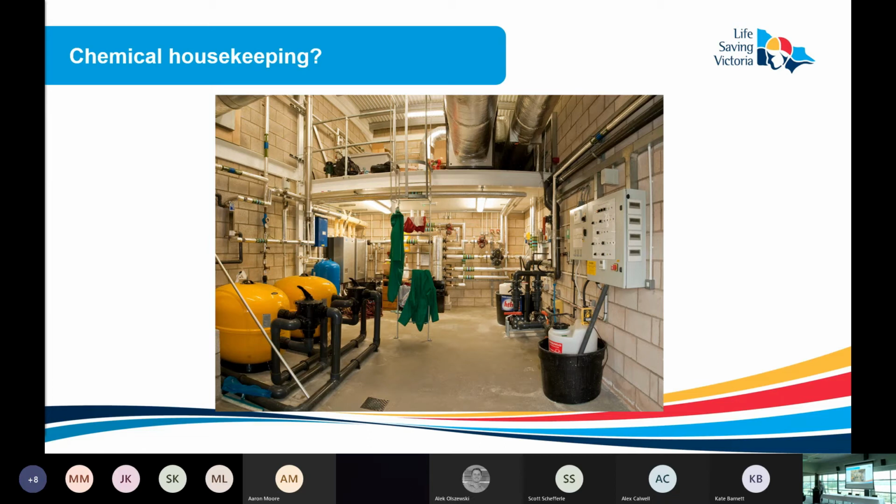You've got regular chemical bunds that can sustain 110% of the capacity of the container that's sitting in it. That's what we're always looking for. And we've actually got a fairly neat and tidy space that you can work in, except maybe for the PPE storage, which is a bit lacking. So if someone was trying to access this ladder up into the upper plant there, it's obviously not a good idea to have the PPE hanging over the ladder that may be required to get up there.